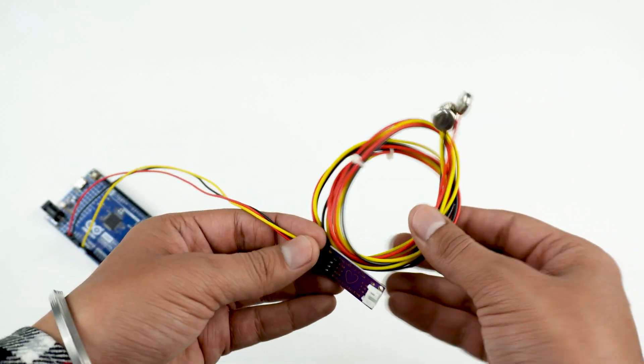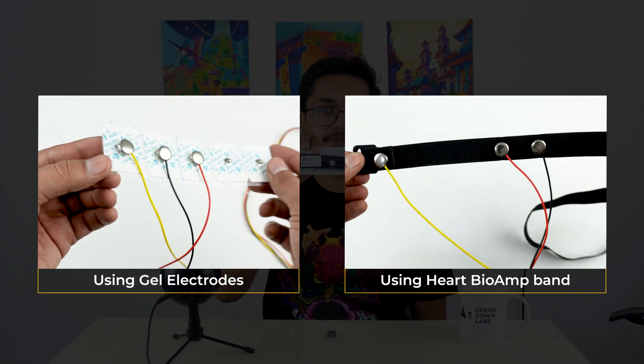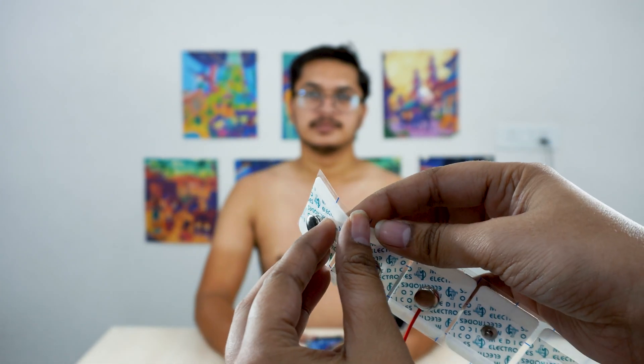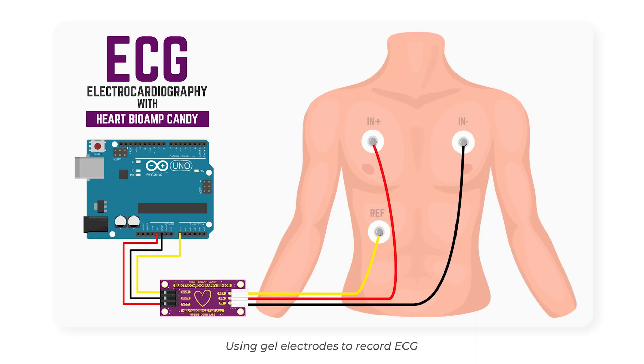Now let's connect BioAmp Cable V3 to Heart BioAmp Candy. You have two options to record the ECG signals — either using gel electrodes or using a dry electrode based ECG band. First, let's use gel electrodes. Peel the plastic backing and place the IN negative, IN positive, and reference electrodes as shown.